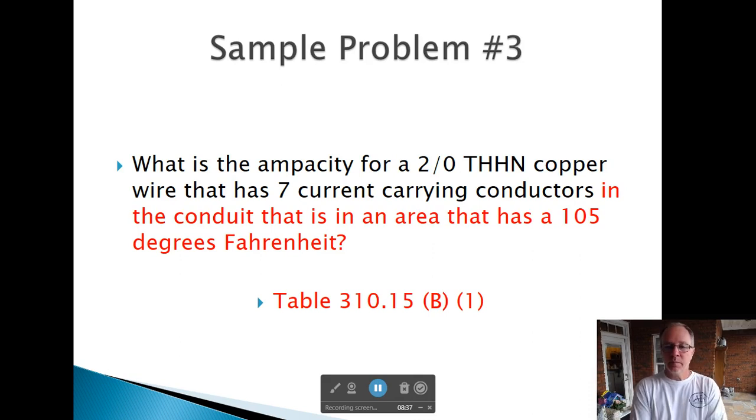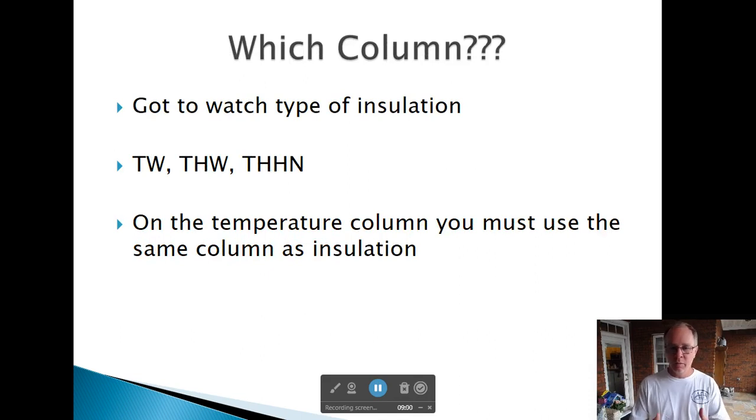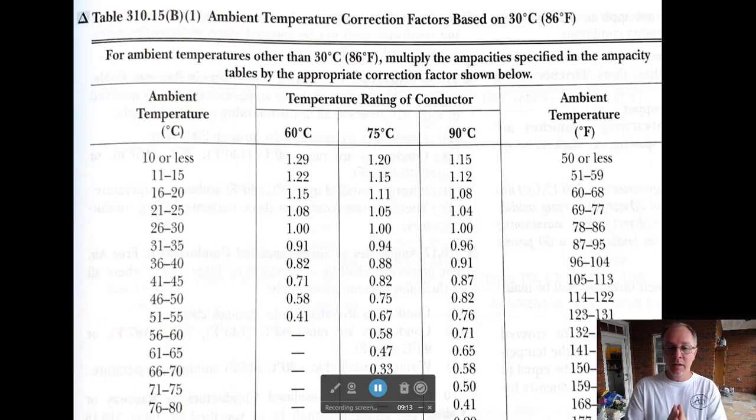Here's sample problem number three. What is the ampacity for the 2-Aught THHN copper wire? It has seven current-carrying conductors in it and it's 105 degrees out there. Well, 105 is above 86, so obviously we're going to go lower than what we had before. Which column do we go in? We need to make sure we do the TW, THW, THHN, or you could say the 60, 75, or 90. But we've got to stay on it.